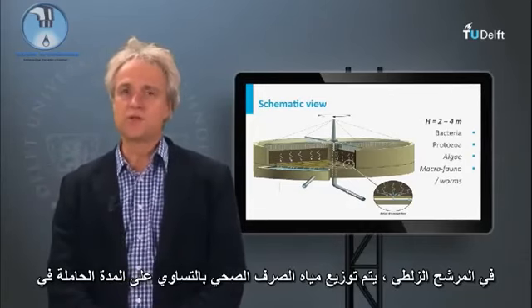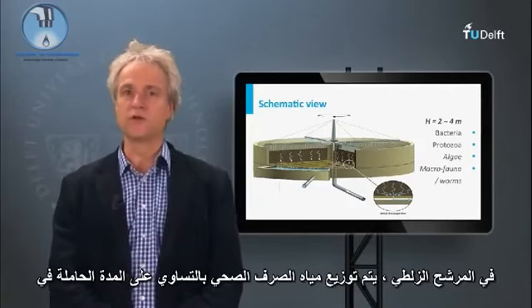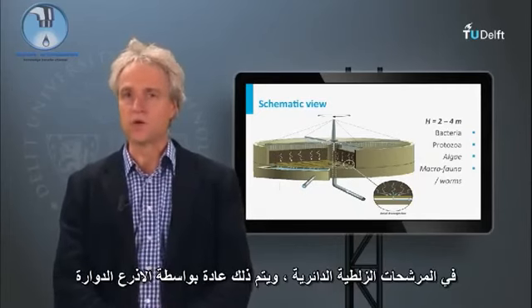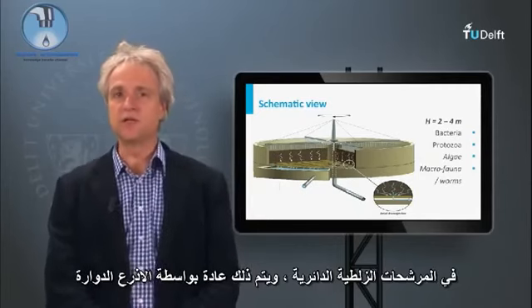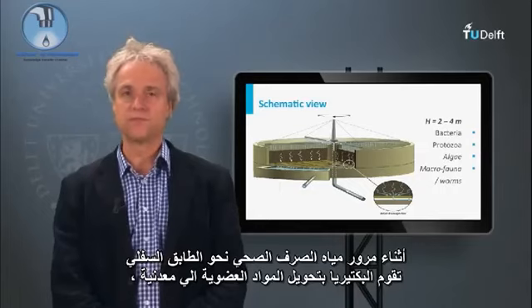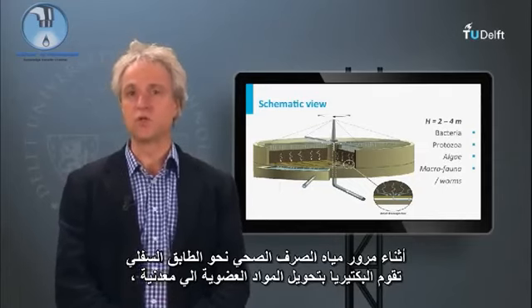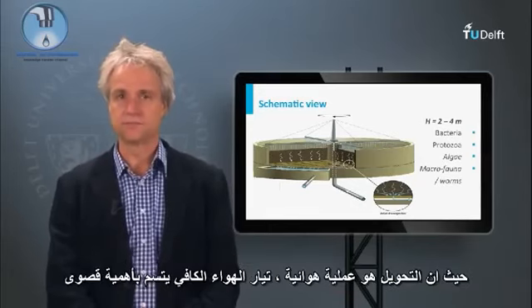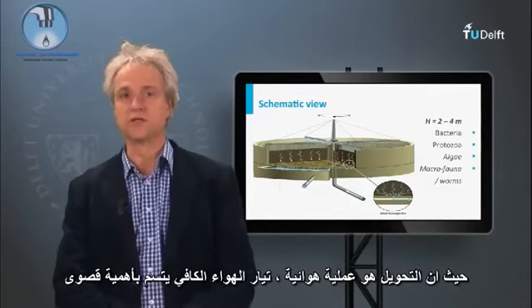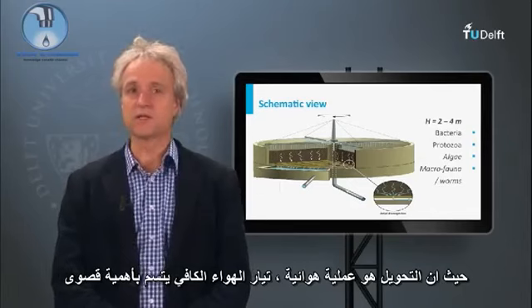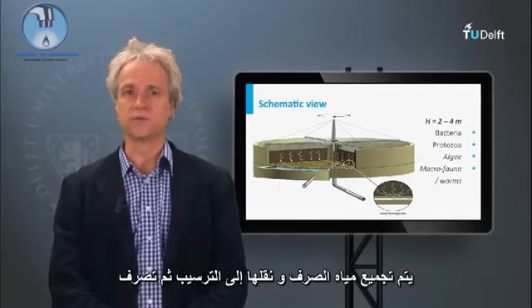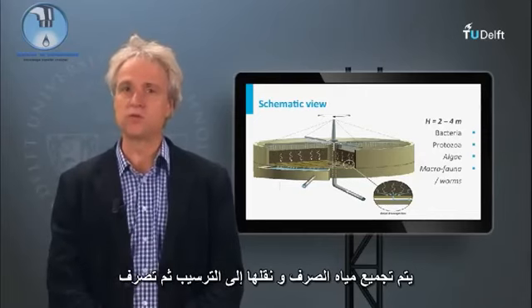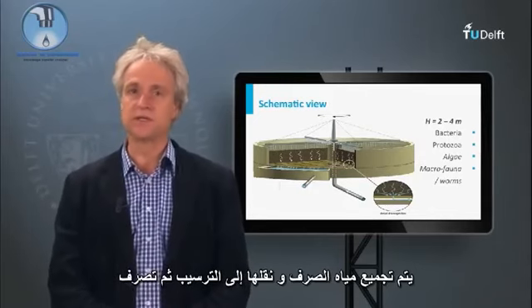In a trickling filter, the sewage is equally distributed over the support material at the top part of the filter. In a round trickling filter, this is generally done by rotating arms. During passage of the sewage towards the bottom floor, bacteria mineralize the organic matter. Since the conversion is an aerobic process, adequate air supply is of utmost importance. The drain water is collected and conveyed to a clarifier and subsequently discharged.